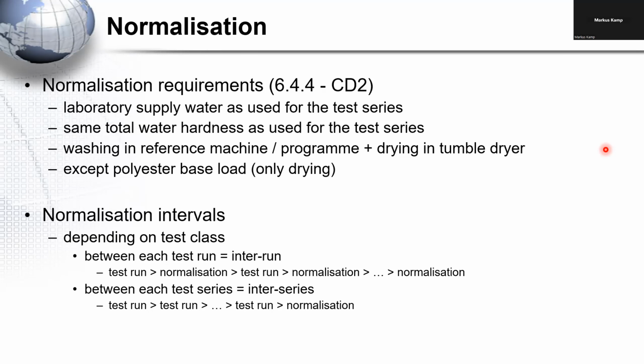The normalization intervals depend on the test class or test design you are using. So if you have an inter-run test design, that means that you have to normalize the load between each test run. That means you run a test run, you do the normalization, you do the next test run, next normalization, and so on until the end of the test series.